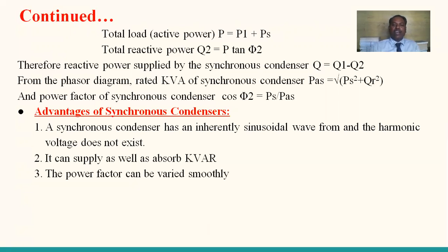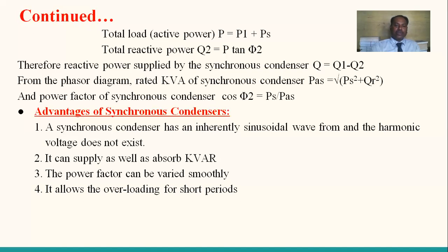And the power factor can be varied smoothly. Why? Because the system is a rotating system. It is not a stepwise variation. It is smoothly varying, so the reactive power, either absorbing or injecting, will vary smoothly. And it allows overloading for short periods. Sometimes, due to faults, there may be excessive voltages in the system. Therefore, the synchronous motor has the ability to absorb the excessive overloads during short periods.